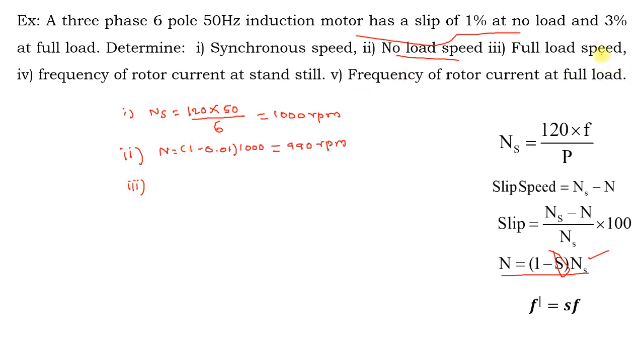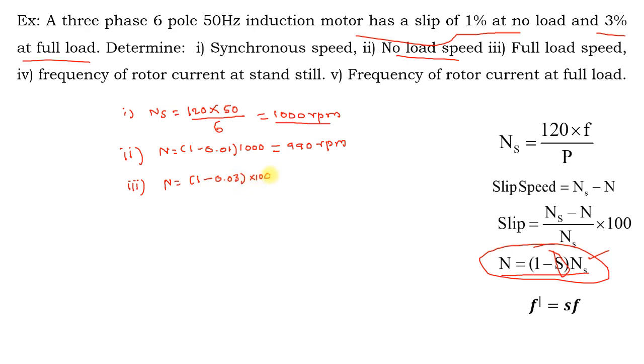Third, find full-load speed. ns is fixed at 1000 rpm and slip at full load is 3%, so s = 0.03. Full-load speed = (1 − 0.03) × 1000 = 970 rpm.